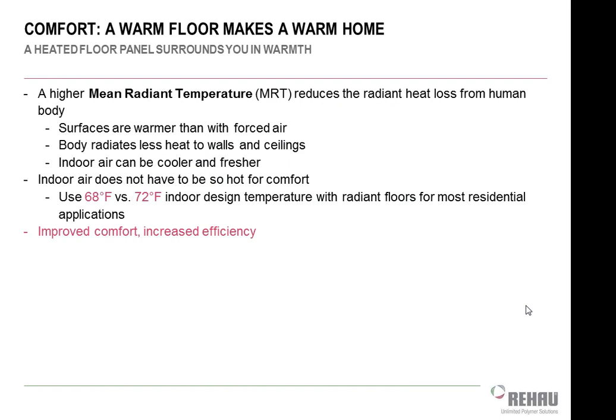Well, in a normal space, the human body has a 98-degree internal temperature and a 91 or 92-degree skin surface temperature, so that 92-degree skin is shining on all the objects. Your chair, your couch, your desk, your floor, those things are all between 55 and 75 degrees in the wintertime. Your body is shining energy onto those things. So when you walk past a cold window, you literally feel cold because your heat is being sucked from your body to that cold window.